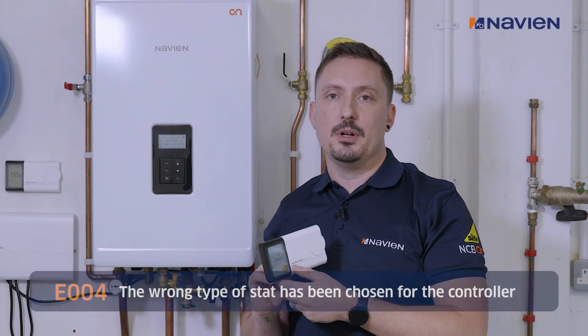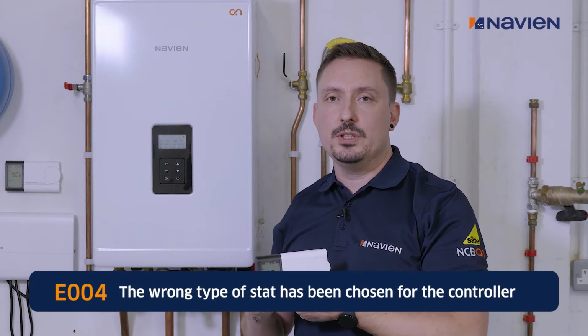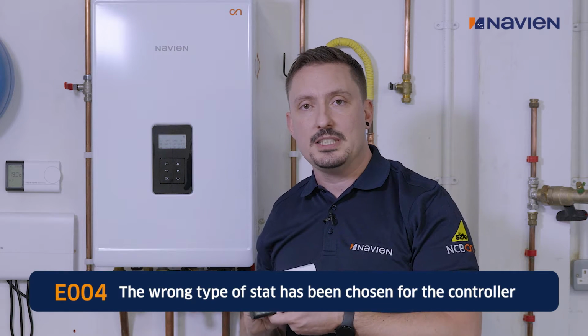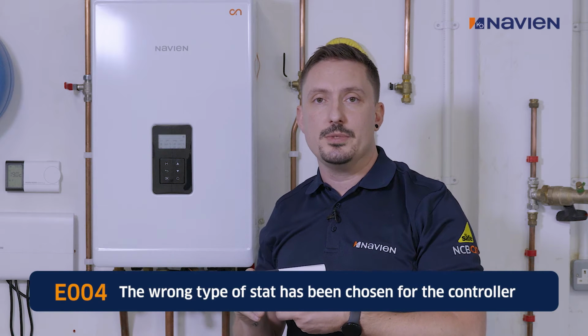You then have E004, which, if you're using the wiring center for a system boiler with an unvented or cylinder stat, you've got two connection types there. You've got an NTC temperature sensor or a cylinder stat. So it just means you've chosen the wrong type of stat for that controller.